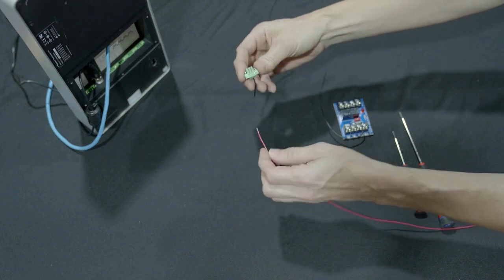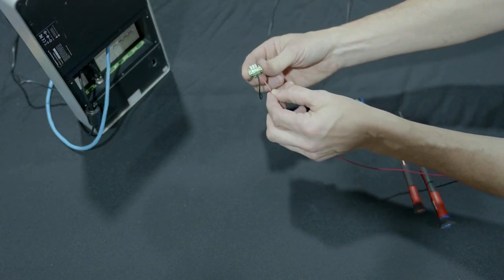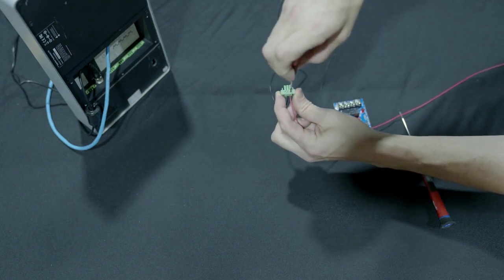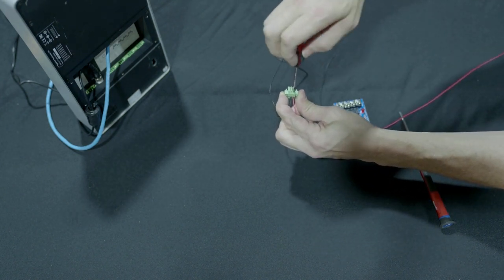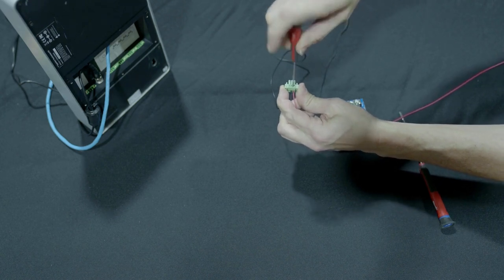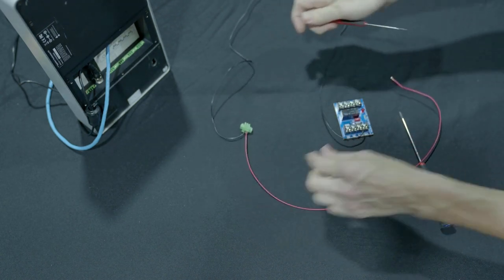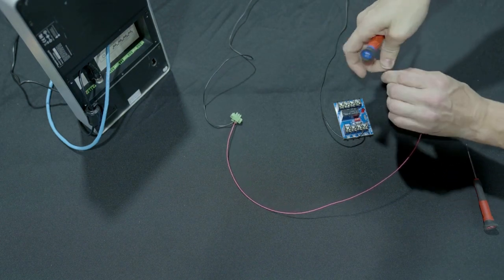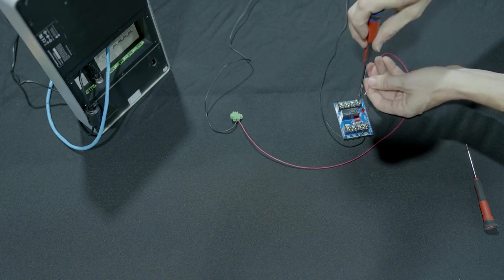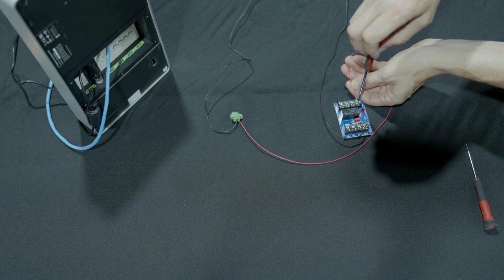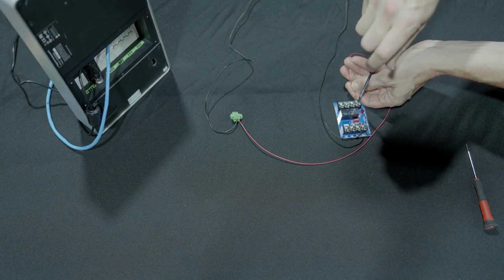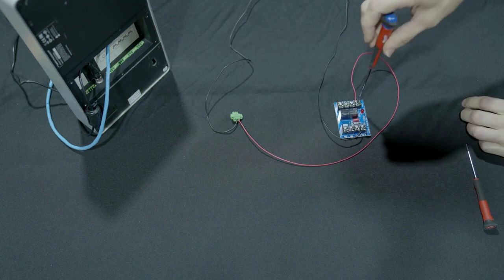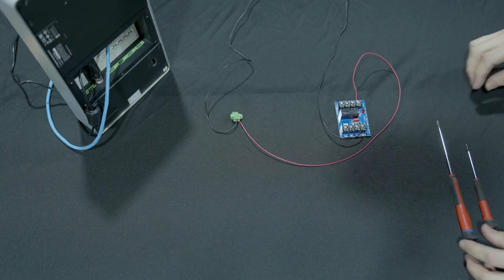Now we prepare the conductor for the connection from the ButterflyMX normally open port to the RB5 relay. For our purposes, we have chosen to use the color red for this conductor as we are using black for the strike side. You can choose your own color scheme. This conductor is the negative one in this circuit. We strip away the insulation and cut off the rest of the wires in the cable. If desired, you can also twist them into the insulation. We do this on both ends, retaining only the wire of the chosen color. In real installations, this cable would be much longer. Please refer to our documentation guide on cable length and wire gauge relationships.